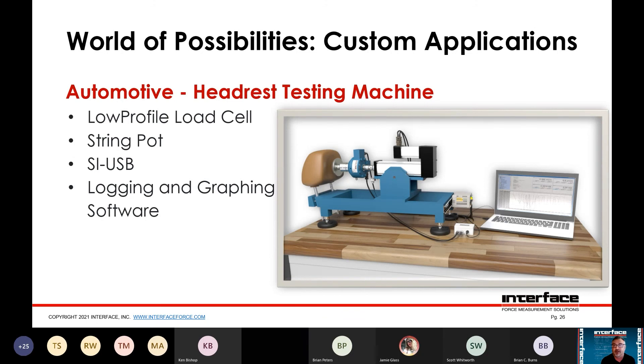This setup was built by a customer, but we provided the load cell, software for collecting data, and a string pot. The string pot and load cell data go into software that logs position versus force as the system cycles. It's a dual-bridge load cell — the second bridge goes to the motor controller that controls the actuator, which the customer programs to run a certain sequence of cycling events while measuring data. If desired, they could run an active control loop to stop the test if it exceeds certain travel. The load cell and string pot feed into our SI-USB, a two-channel device that accepts load cells, high-level inputs, and various other sensor types.